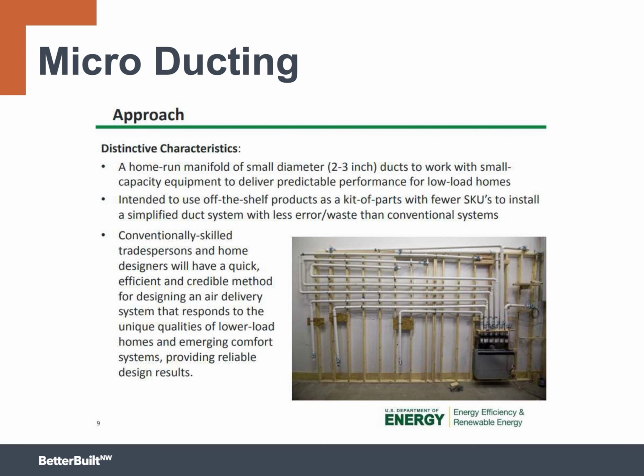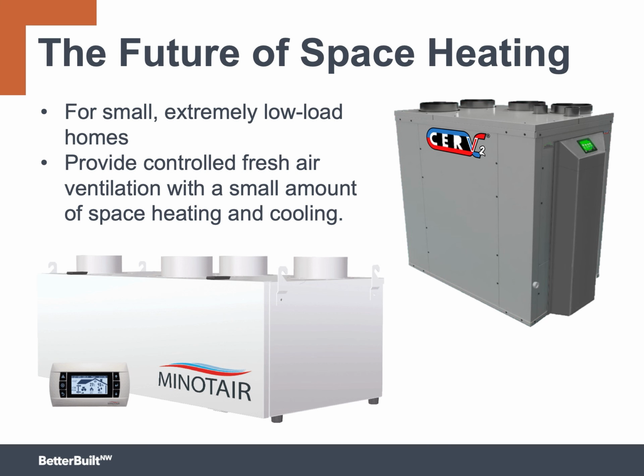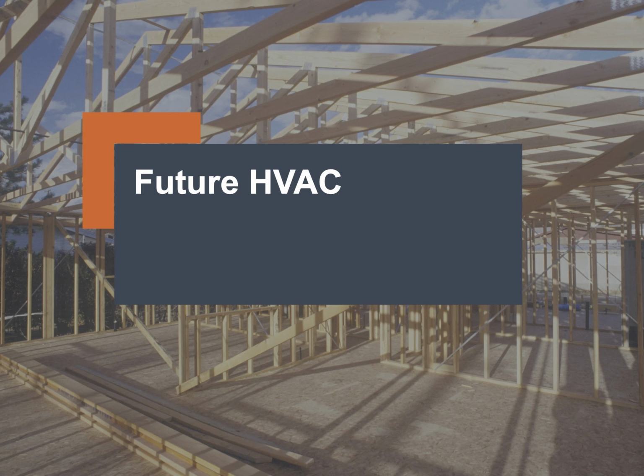The 3-inch ducts allow the builder and the HVAC trades to run ducts in between standard joisted floors and up and down the walls, even 2x4 walls. It works well for lower load homes with good envelopes. Small, super high performance homes, such as those built to Passive House or Zero Energy standards, should consider a highly efficient heat recovery ventilation system. These two units use heat pumps to recover heat and have a small amount of space heating and cooling capacity. If the building loads are small enough and the climate is mild enough, one of these might be all you need. Like everything else, the HVAC industry is developing advanced systems to meet the needs of the future.